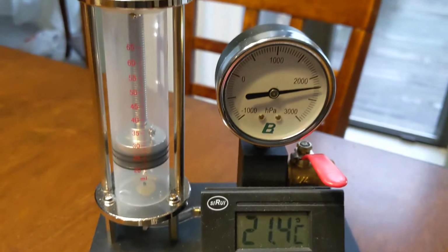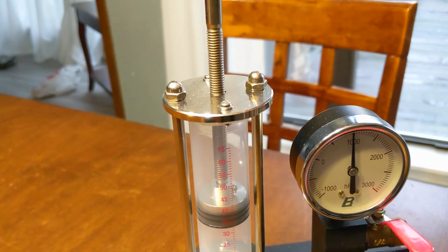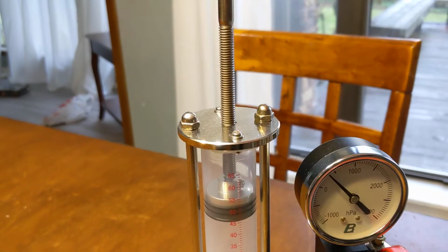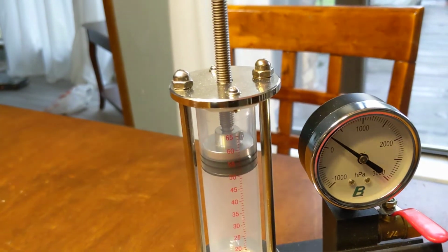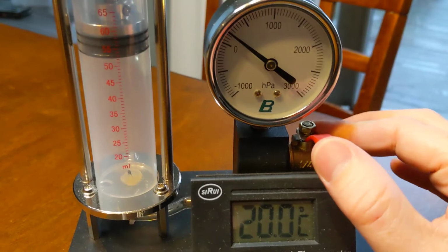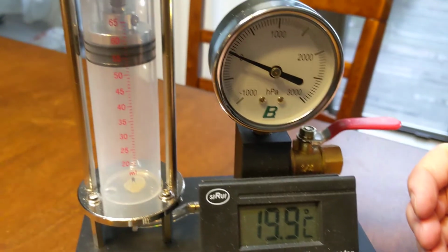All right. So this, by the way, is how I was changing the pressure. It's just a little screw essentially that is attached to a plunger, and we just turn the screw and it brings the plunger up and down. And I'm going to bring it back up again because I don't want to break the sensor inside of there. If you just let the gas out when it's really highly pressured like that, then it will sometimes hurt the apparatus.